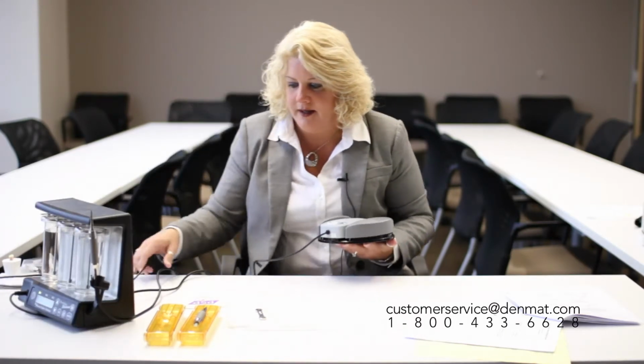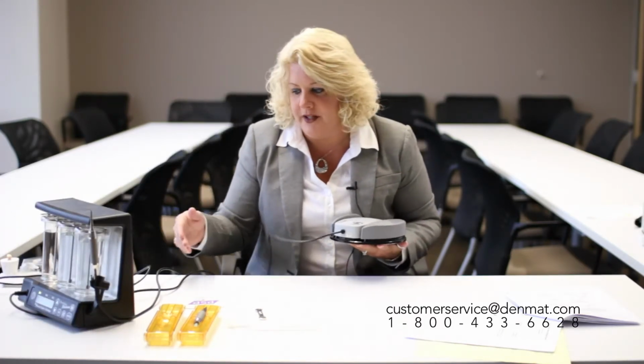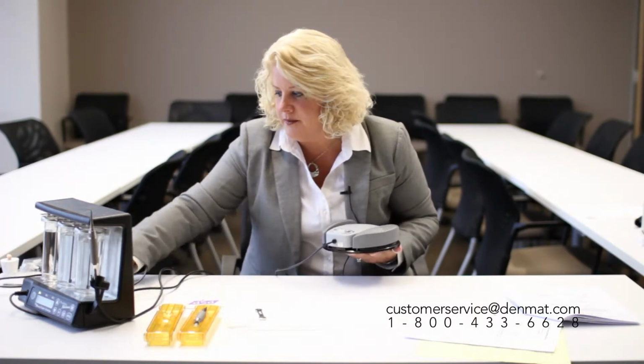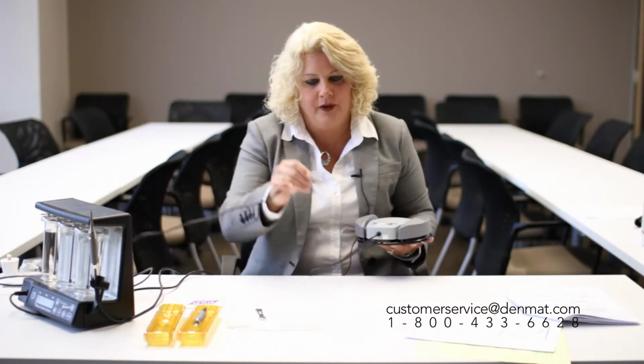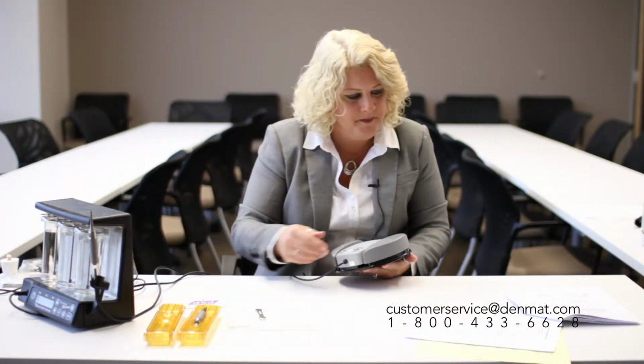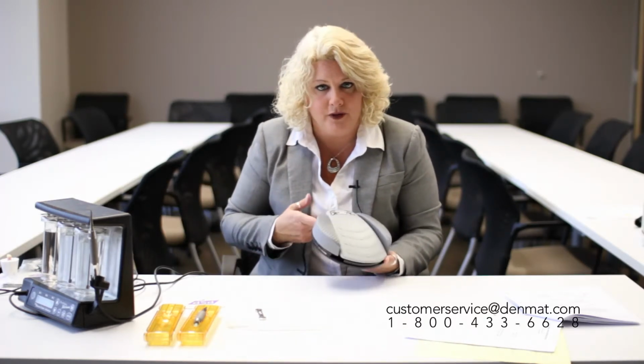and unplug the foot pedal itself from the unit to see if that stops the water from leaking. So we'll ask you to unplug the foot pedal with the gray plug and see if the water stops running out of the handpiece. We'll then ask you to plug it back in to see if that resolved the problem. If it didn't resolve the problem, then your unit is going to need to come in for repair. At first, you can try just ordering a new foot pedal to see if that resolves it, or you can send it in and contact us here at DenMat Customer Service.